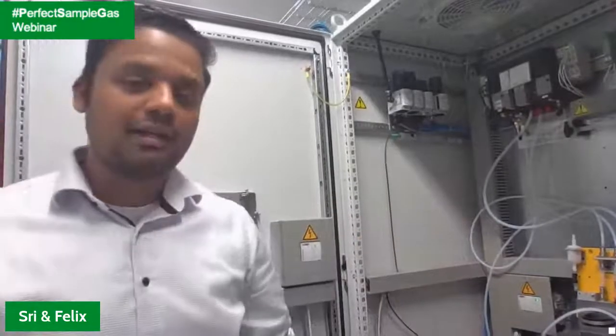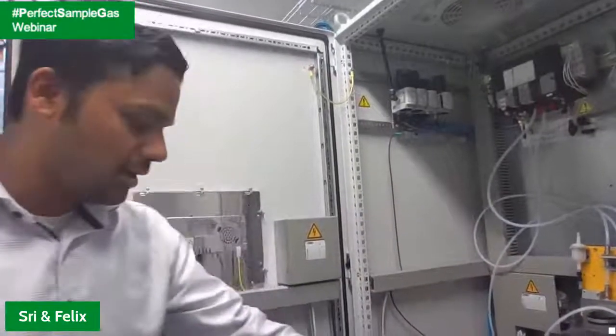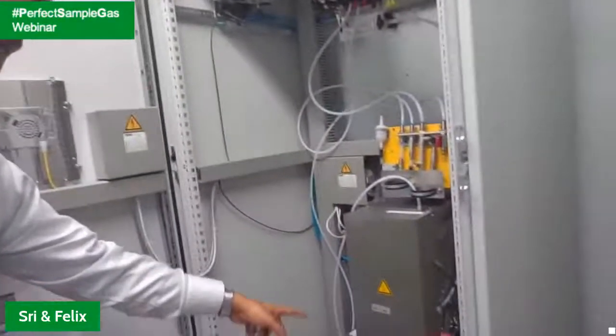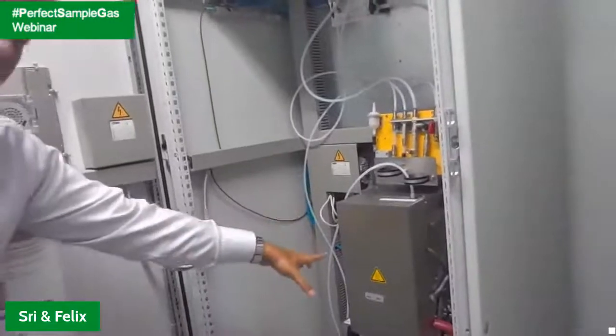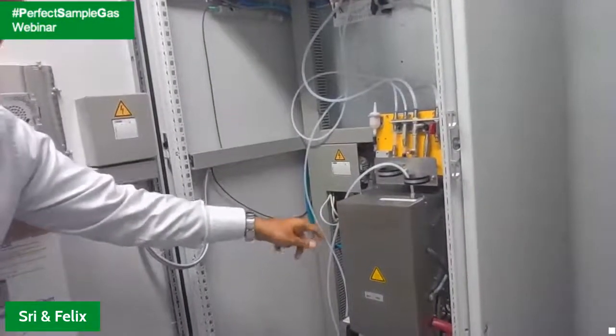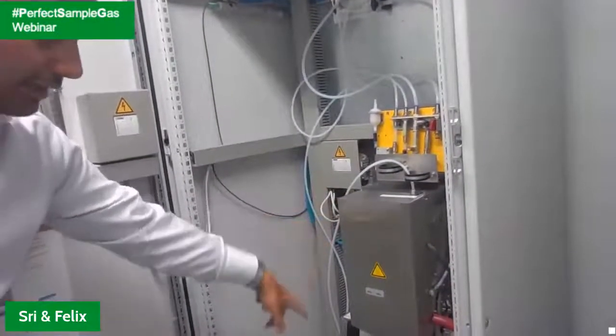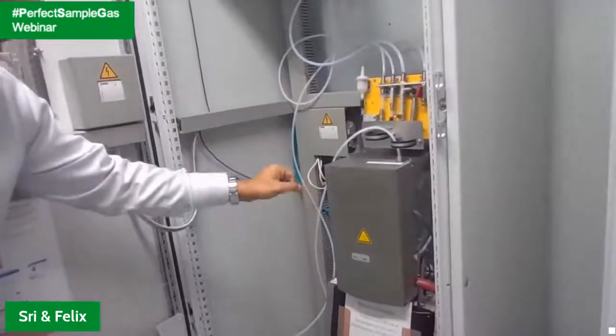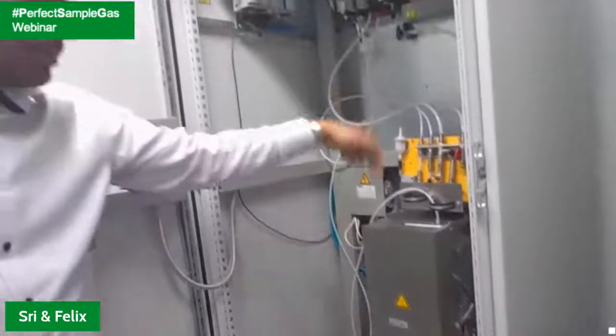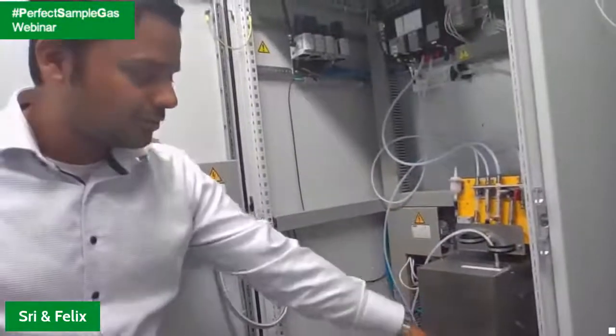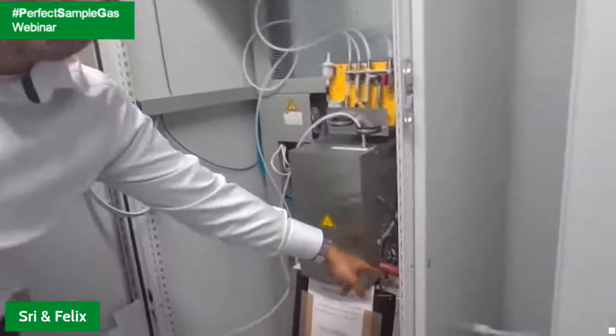This specific analyzer has, if you can see it down, if you don't mind showing this yet - so this is the measurement cuvette, and this is the photometer, where we are bringing in the sample gas from the top, and there's also exhaust outside, as you can see, with the heated jackets.